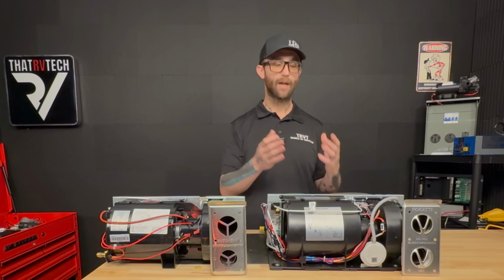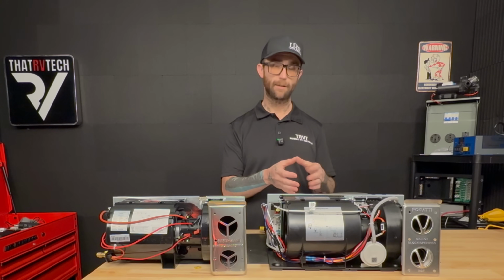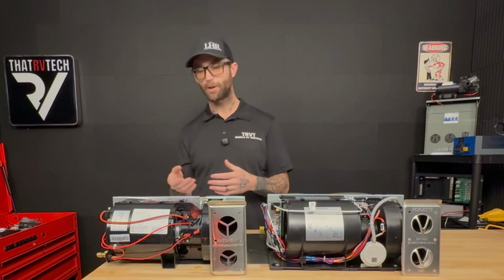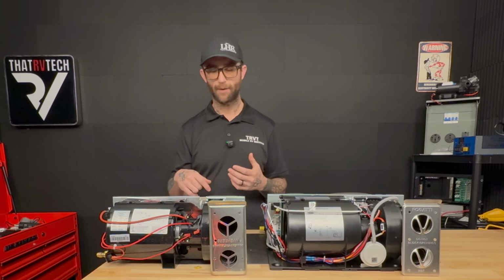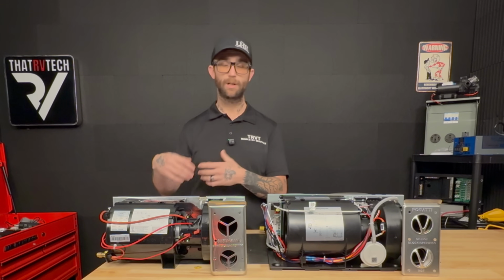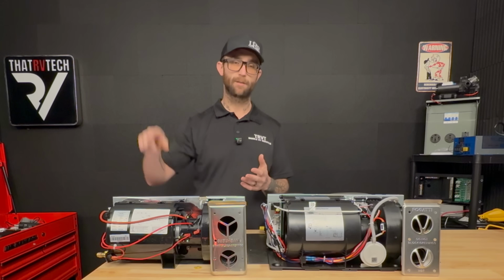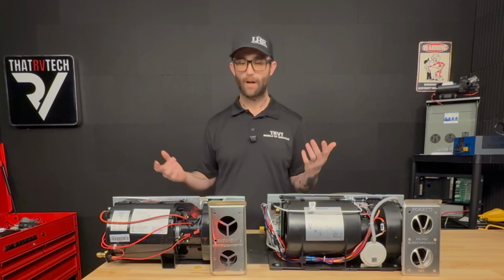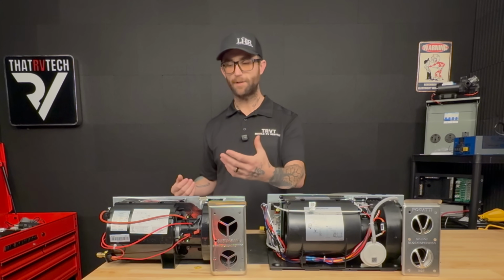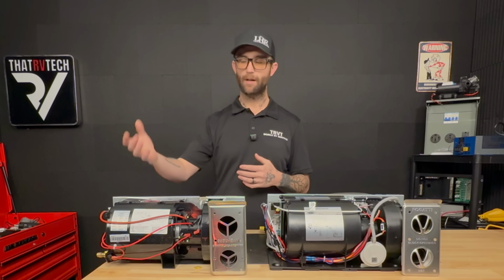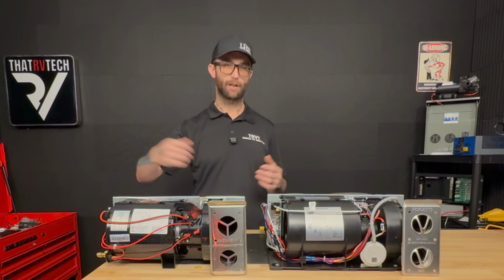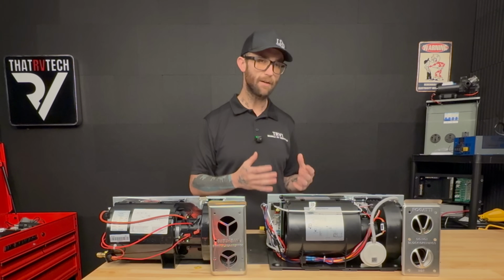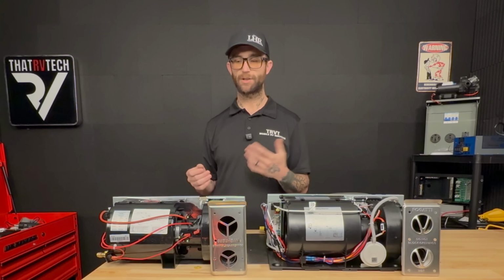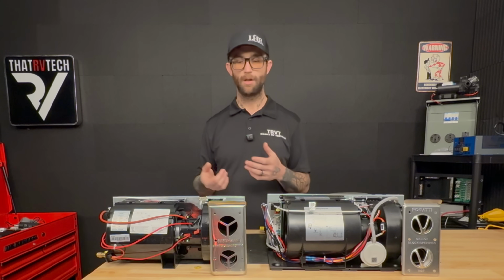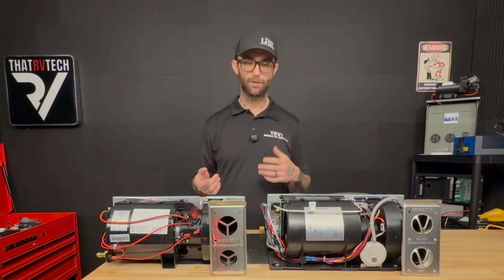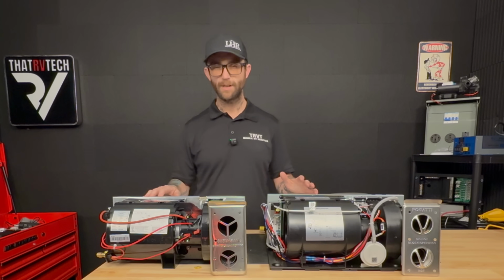That's because every single thing on this furnace is actually wired individually. On a Suburban, you have things that are kind of looped together, like the over limit switch and the sail switch, sometimes part of the same circuit, what I often call the safety circuit. Those are the safety devices of the furnace. So when you get an error code, usually just a series of flashing lights on the control board, they're very, very generic, because it's just telling you there's an airflow issue or a voltage issue. They're not very specific.